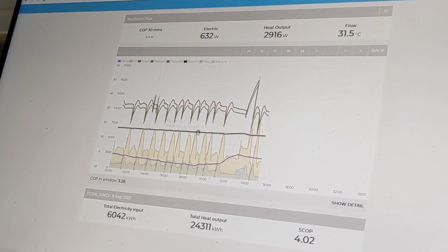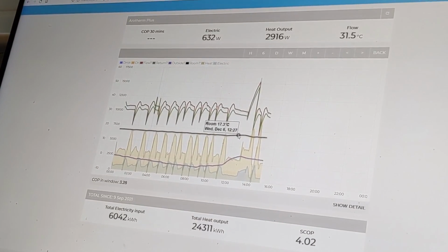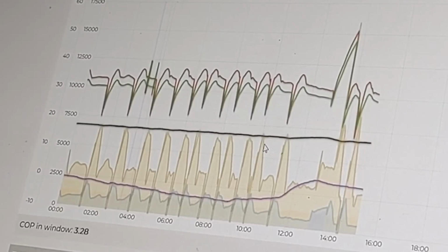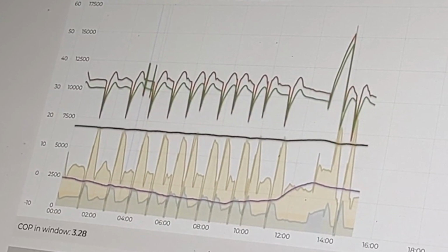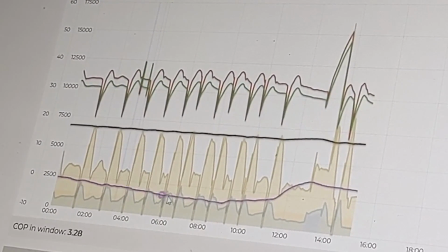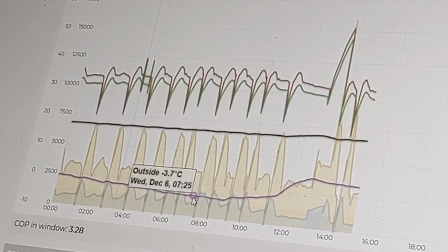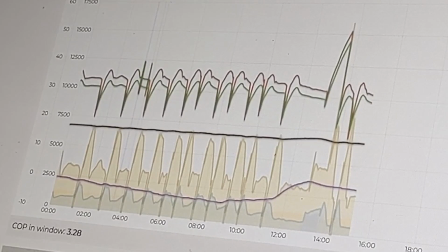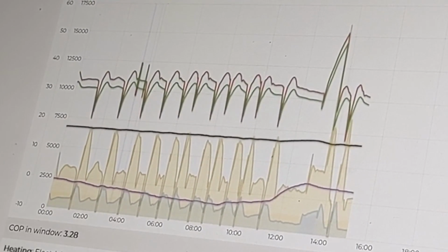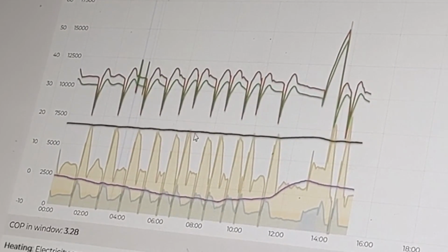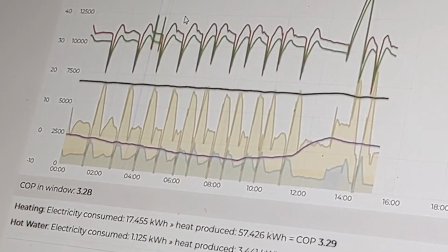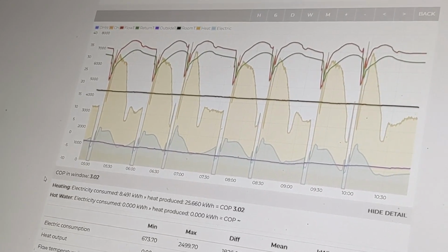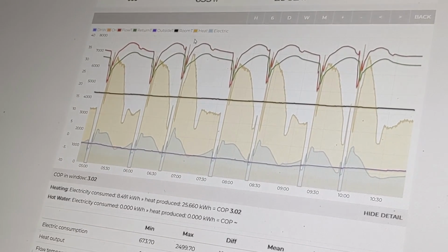I mean, it's anonymous data, but interesting. His room temperatures are lower, because I'm running mine at 19. Maybe his room temperature monitor's in a funny place or something. But that's helping his performance, isn't it? It's probably helping his performance, with minus 3.7 degrees outside. He's probably using infrared heaters. He's a tough Scotsman. So that's actually helping him with his coefficient of performance.